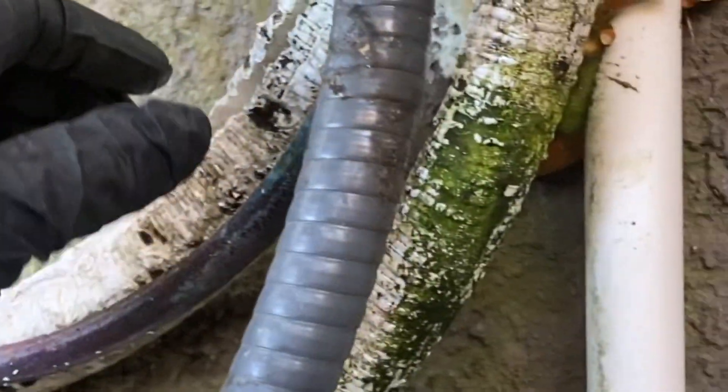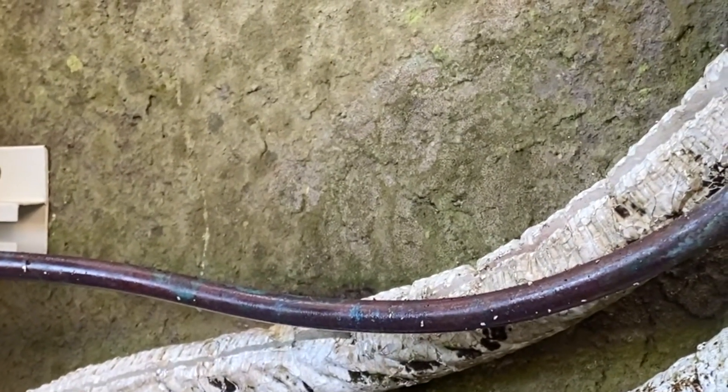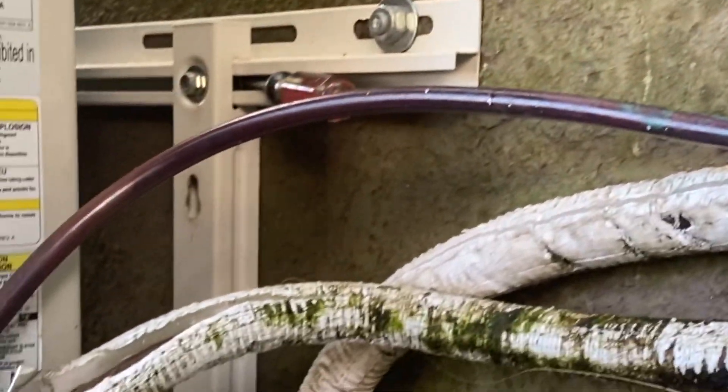These are preset copper lines that come rolled up, already wrapped in white Armaflex. We've run into issues in the past where they develop leaks — many leaks — on these preset line sets that come rolled up.